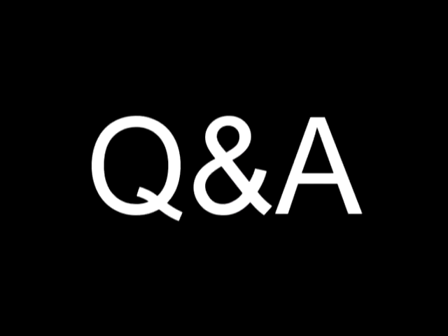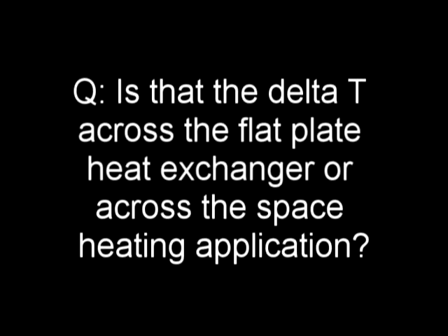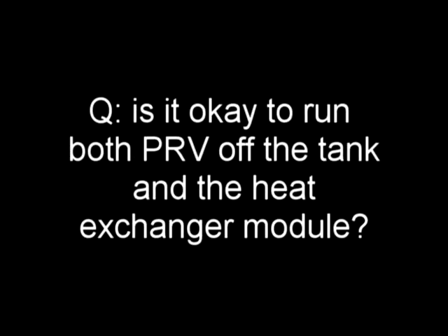I'm going to take a quick break here to look at some questions. Okay, I had a question about delta T across the flat plate heat exchanger. I think I got to that one. That's 20 degrees delta T. Is it okay to run PRV off the tank and the heat exchanger module? Yes, you can combine them by code.